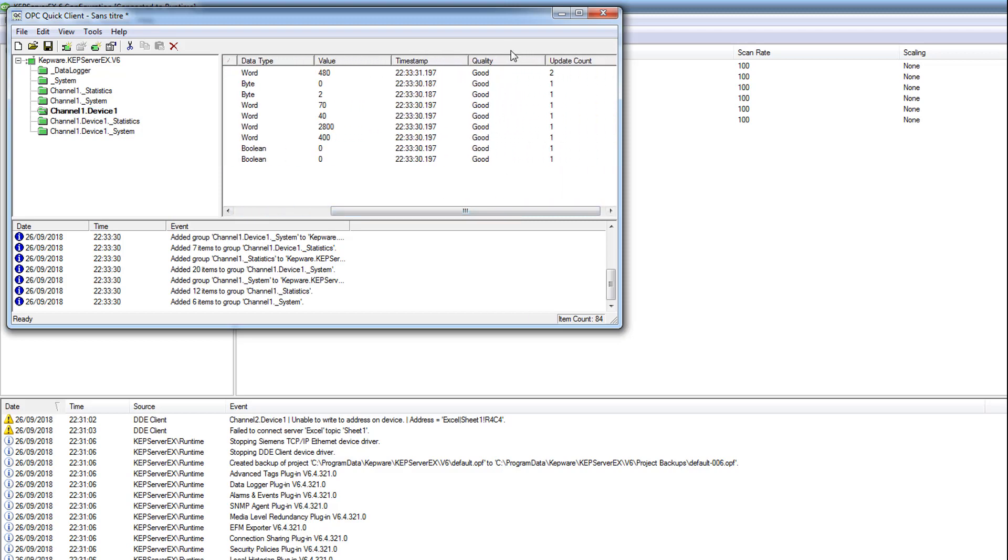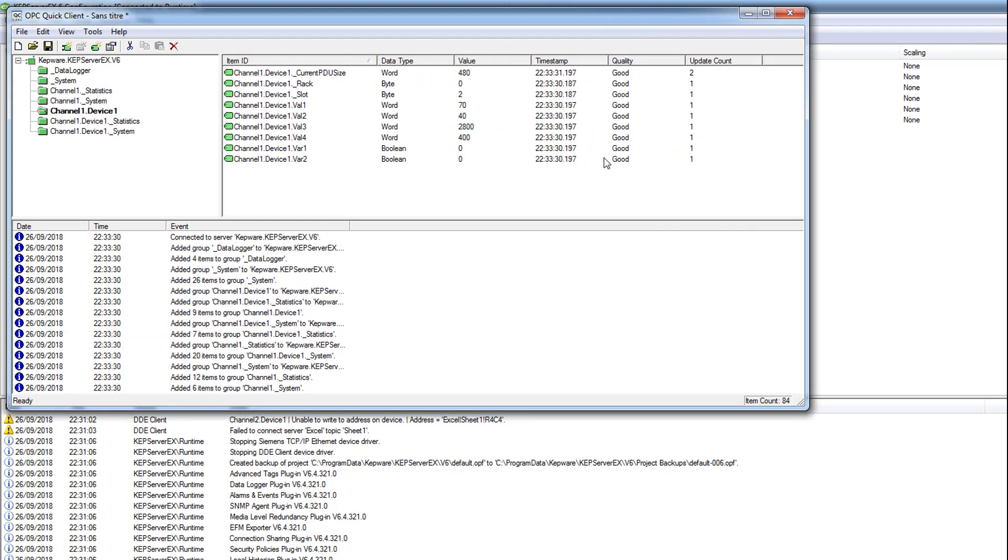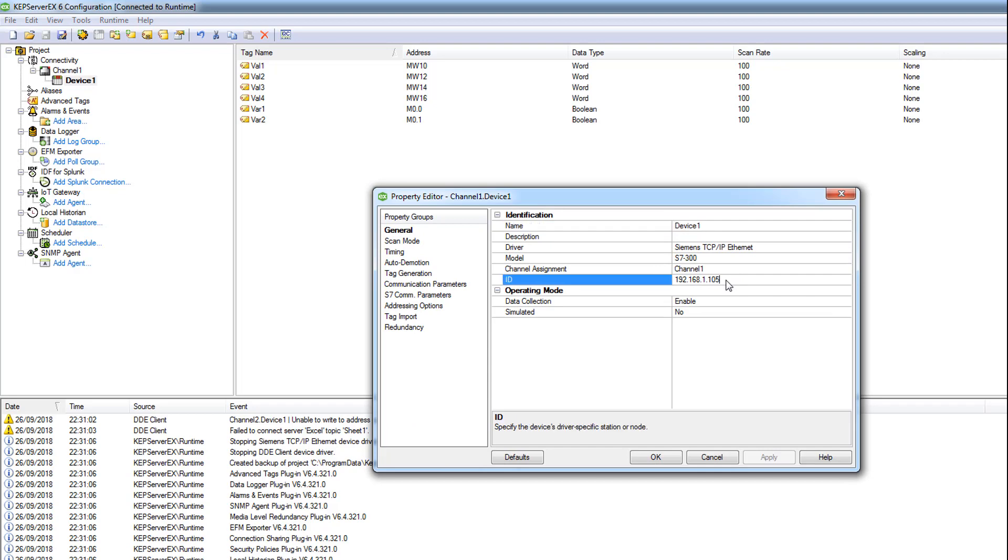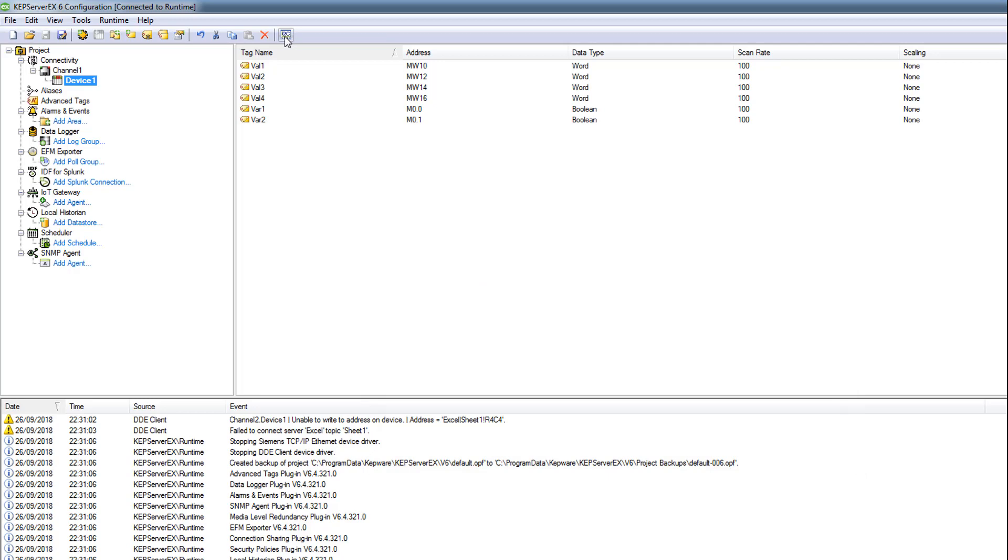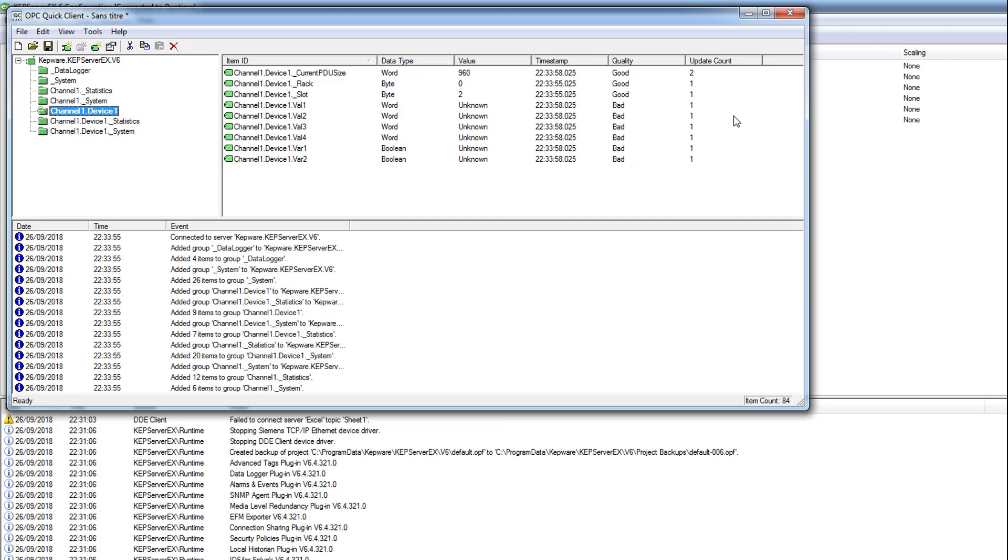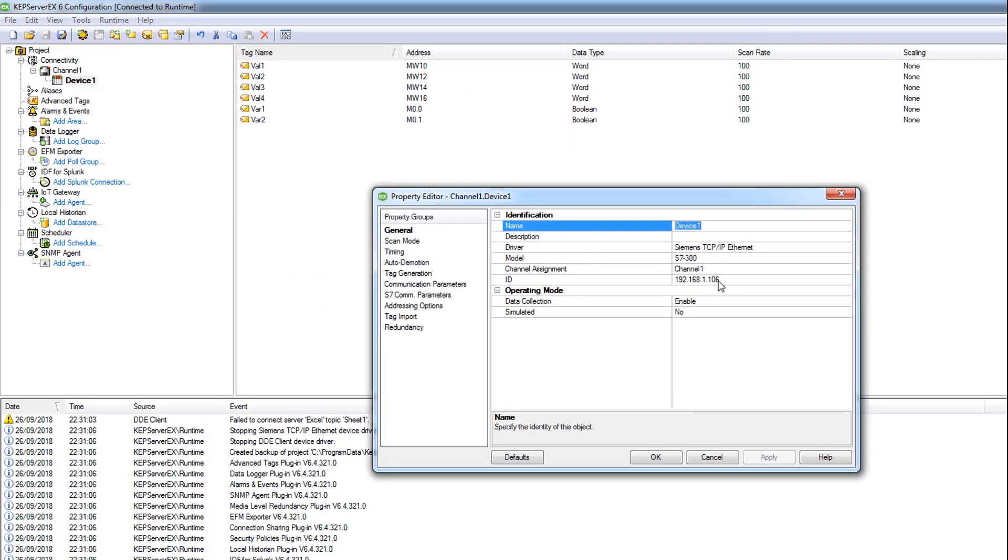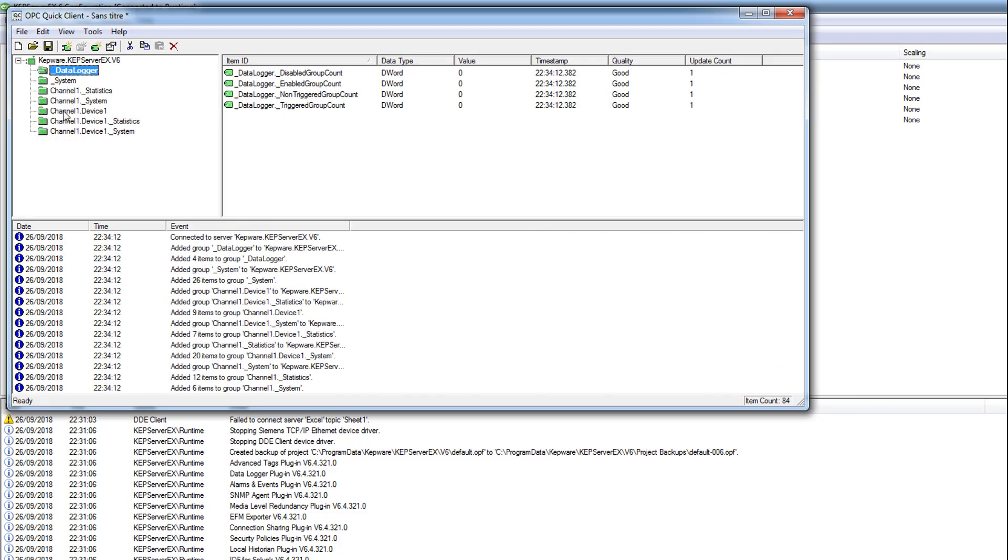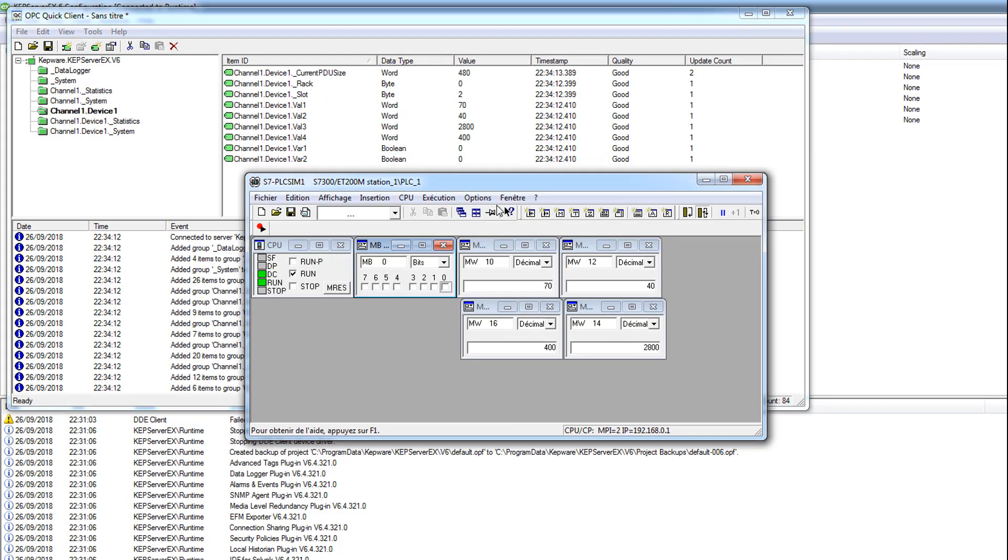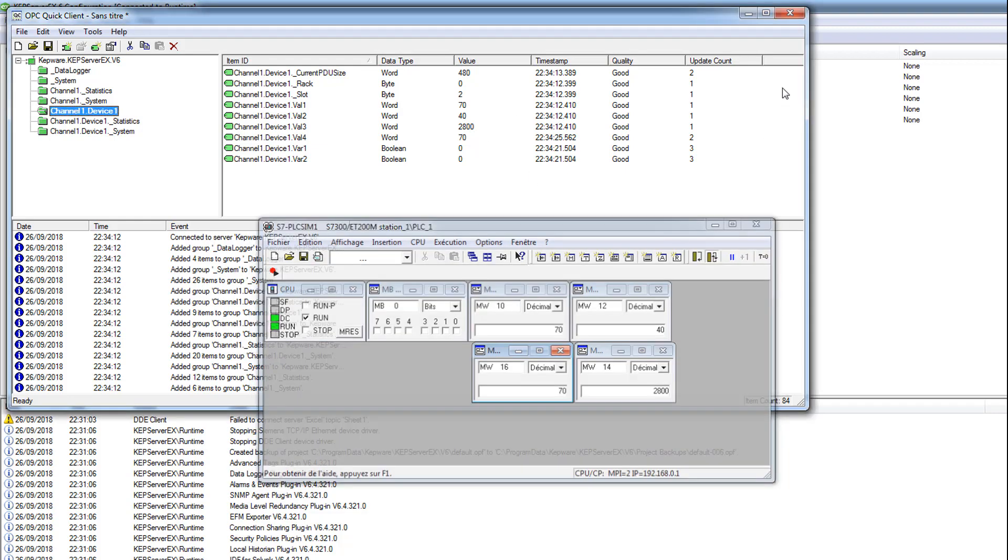You check always the quality if it's good or bad. If something's wrong in the connection, you're gonna get quality as bad. You can check it if you want - if I change the device address, you see it's unknown, quality bad, just because it doesn't have the right address. The quality is very important in here. Everything is okay.